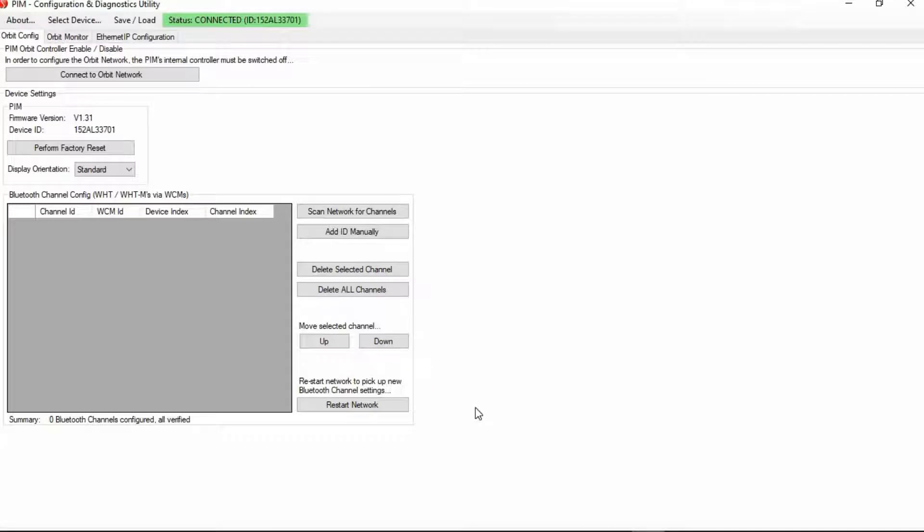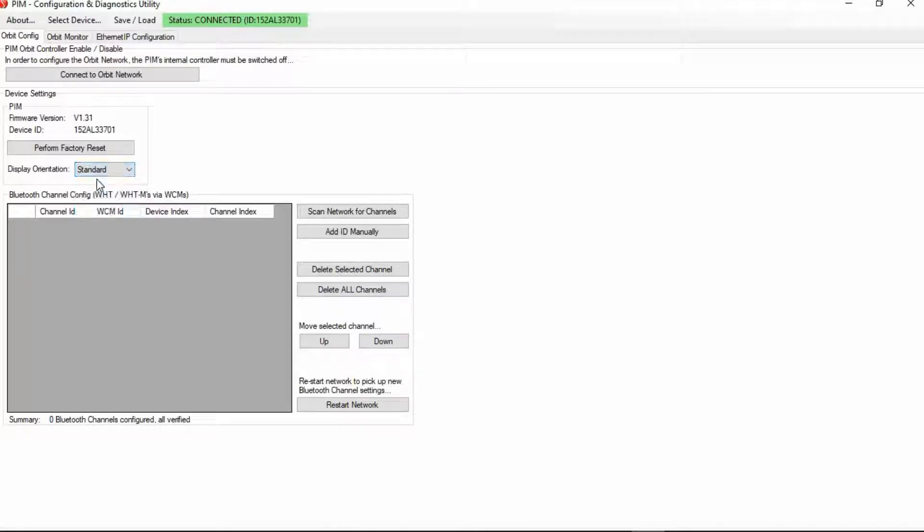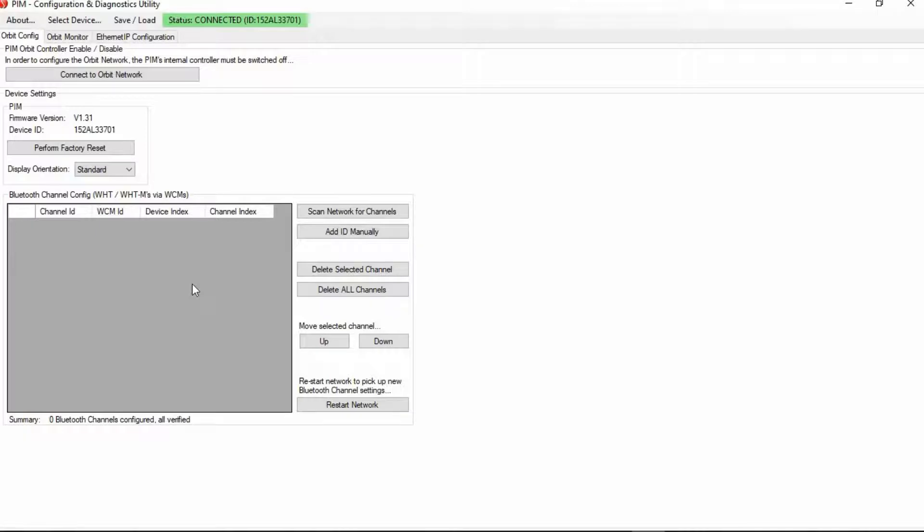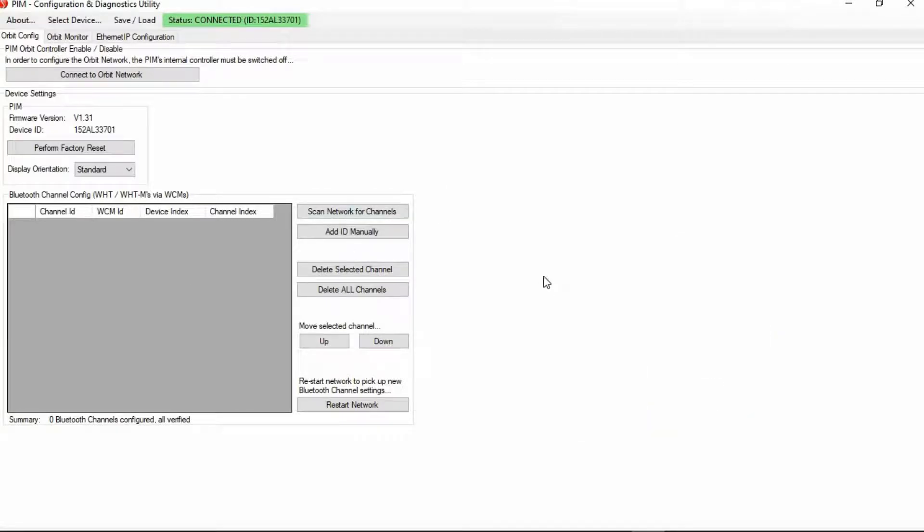And here you have just a couple of basic settings. First, over here, this shows the firmware version of the PIM. And then this is a button where if you just want to wipe the memory clean for the PIM, you can just click perform factory reset. In addition, this is the display orientation, and that has to do with the display on top of the module in case you wanted to change it to 90 degrees or 180 degrees if it's perhaps mounted in a cabinet in a certain way. Then down here, this is a particular window for the Bluetooth channel configurations. And this is where if the PIM is connected to a wireless connection module, and then you are communicating with a WeGage or a multi-channel WeGage. And here you can scan network for channels, add ID manually, those types of things.